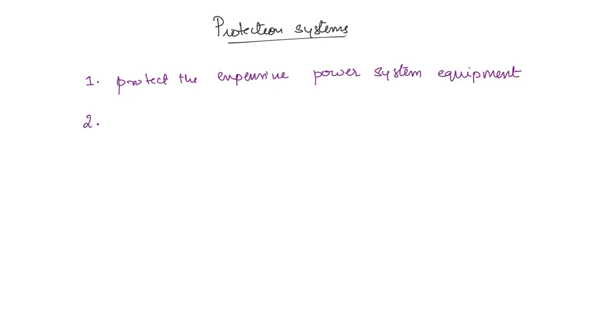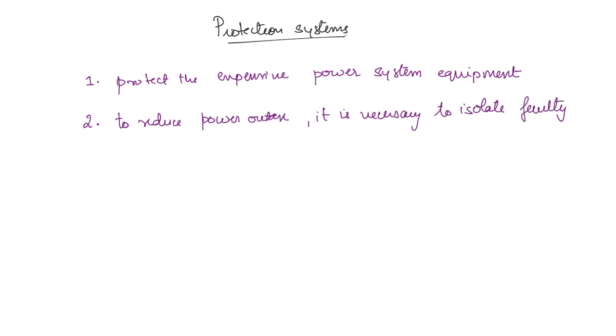And second, obviously when there is a fault, the power will not be delivered, right? There will be a power outage. We don't want that, right? So the protection system helps isolate the faulty network so that the other healthy networks that are present are not affected. The power delivery through the healthy circuit is not affected. So to reduce power outage, it is necessary to isolate the faulty network as soon as possible. So these are the major functions of protection systems.